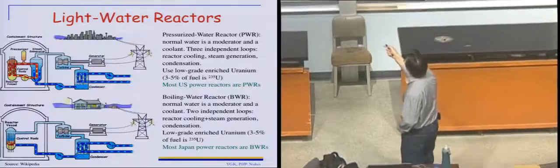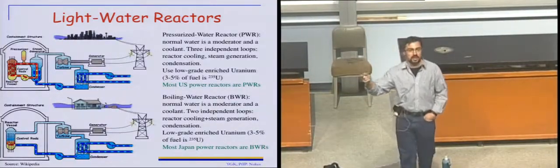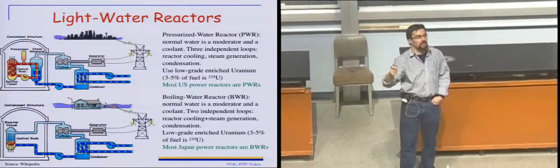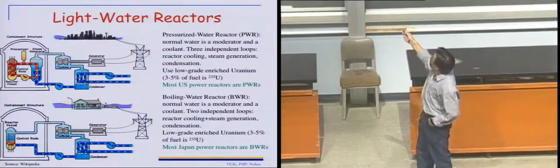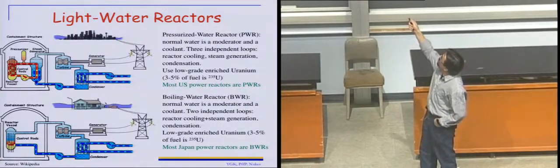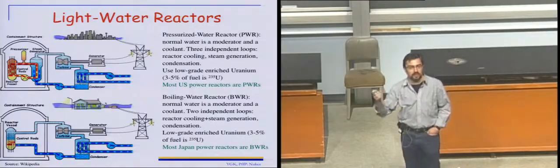But on the other hand, the water that passes through the turbine is potentially contaminated by the fission-produced isotopes. And so the turbine will probably be contaminated as well, whereas in the pressurized system, if everything goes well, the turbine can be clean.